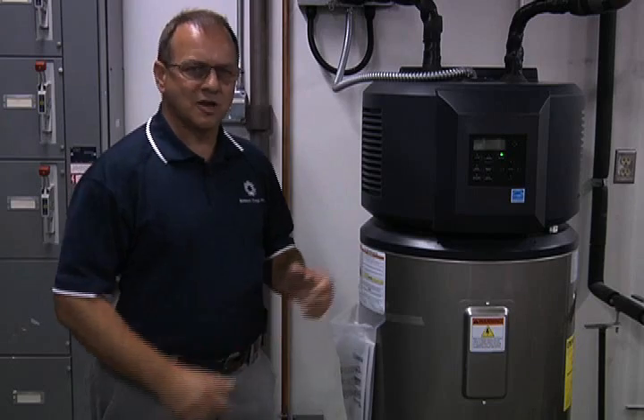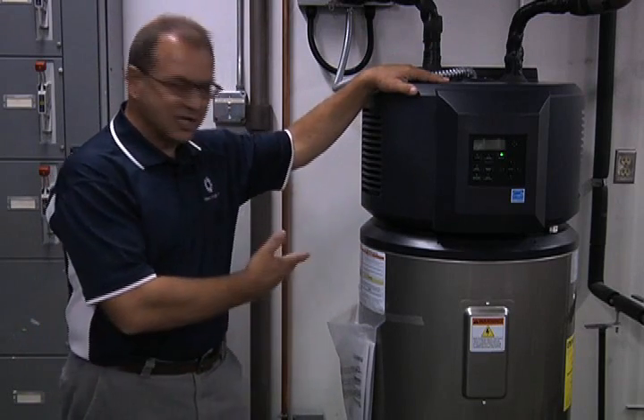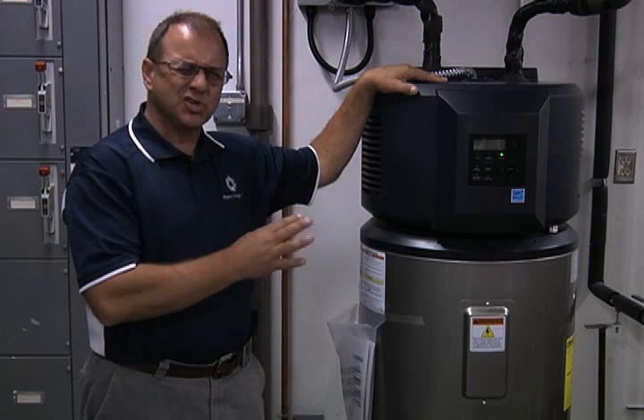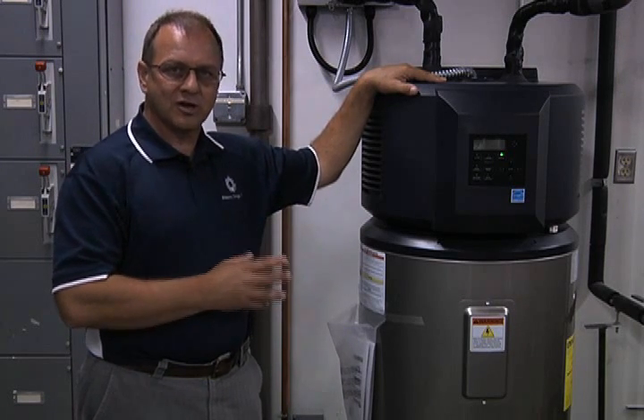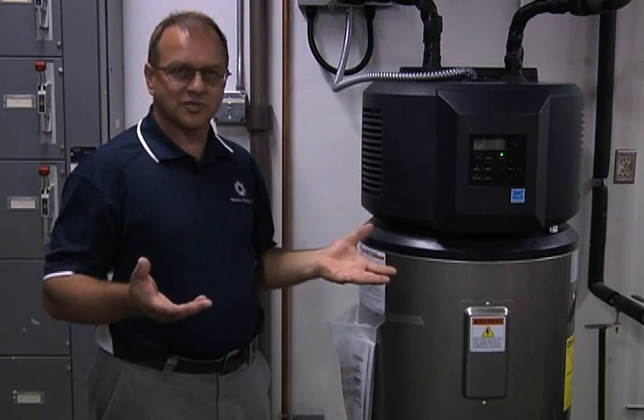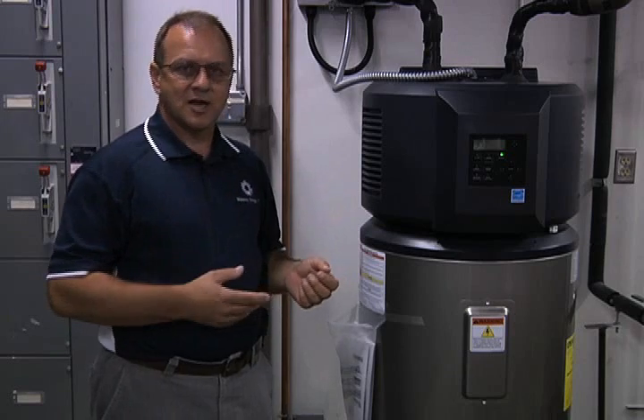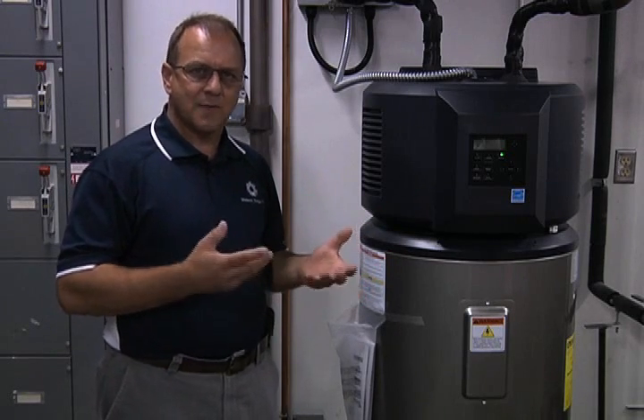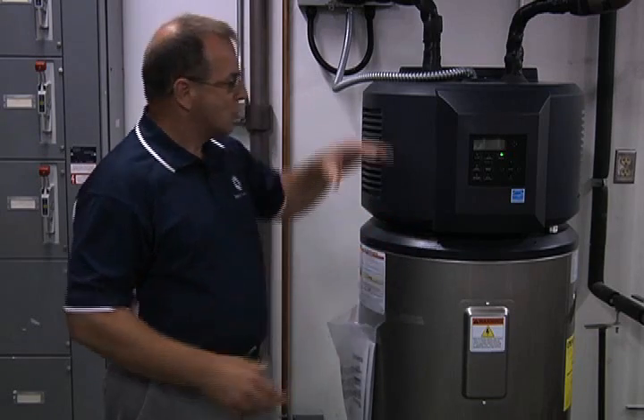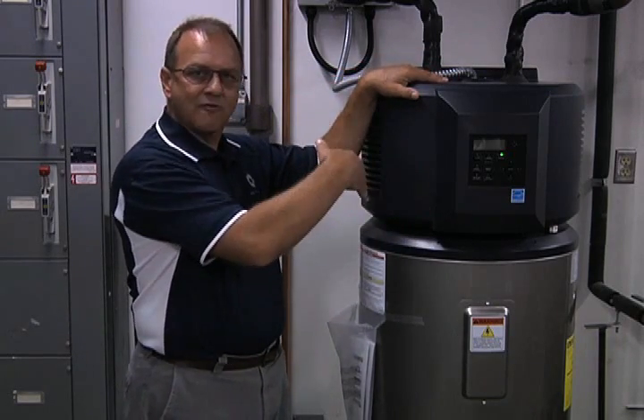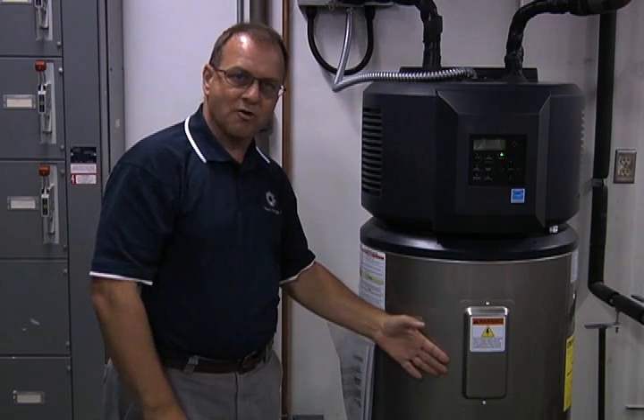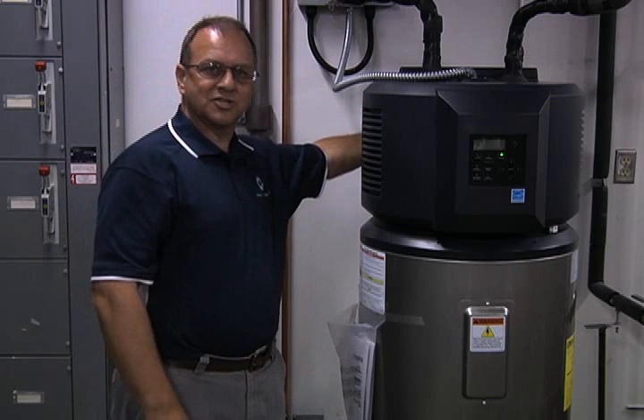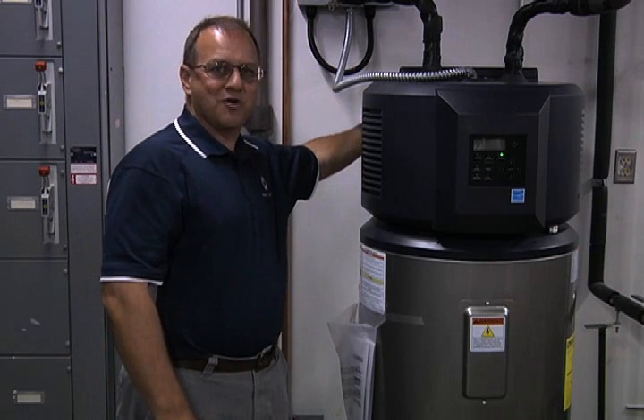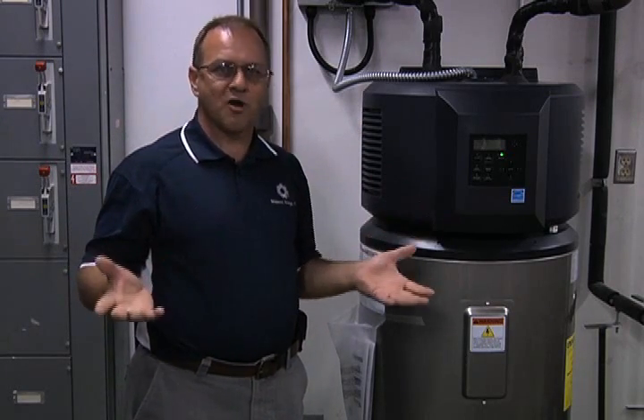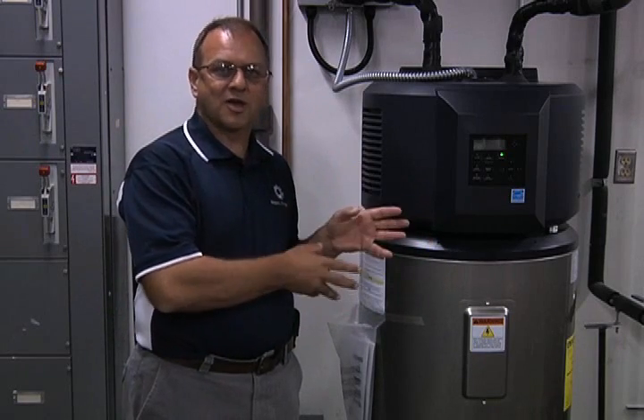We talked in our water heating video earlier about heat pump type water heaters, and this is an example of one we use in our own building. They're about 2.5 times more efficient than a standard electric water heater. We've got a lot of waste heat in this room because of the motors, transformers, UPS systems and other devices that produce a lot of heat. Let's do something with that heat. We've got a device right here that can bring in air from the room, take heat from it, heat our water with it, and then the nice advantage is when it's running, we get cool air. So we actually have a pretty comfortable mechanical room. Not that that's that important, but the thing is, we're taking a waste product, heat, and we're doing something good with it — we're making hot water.